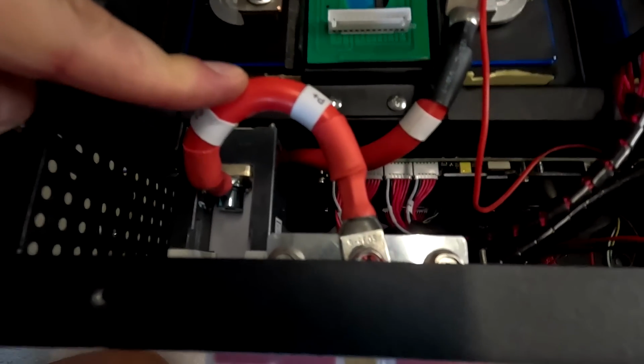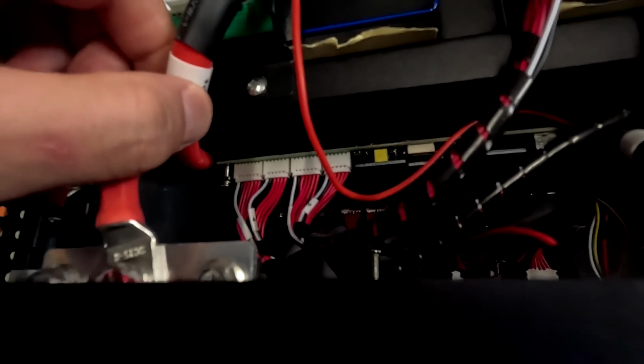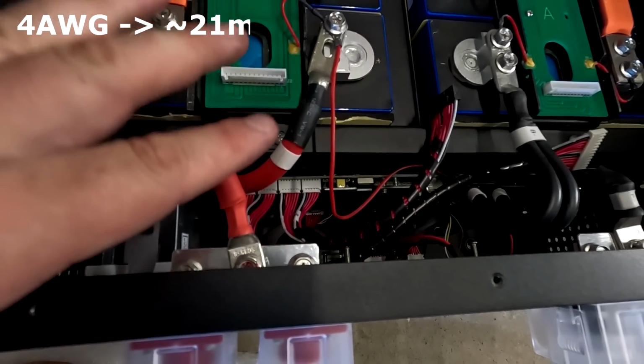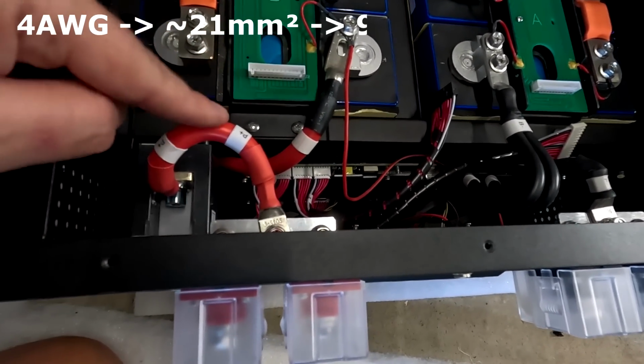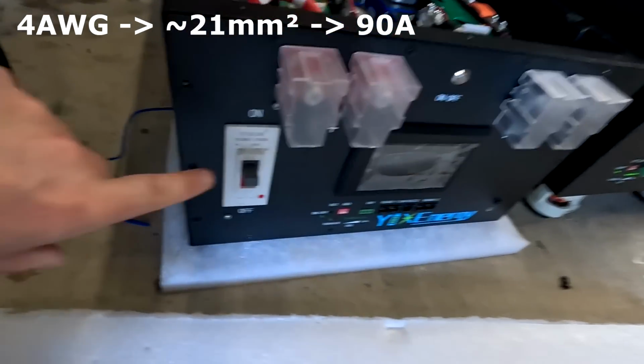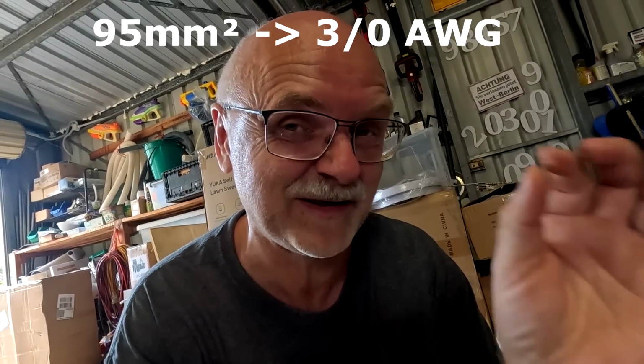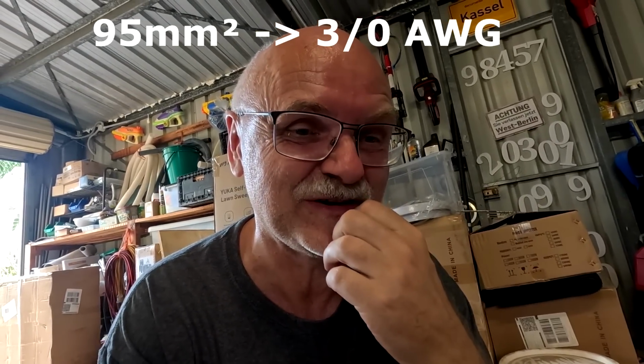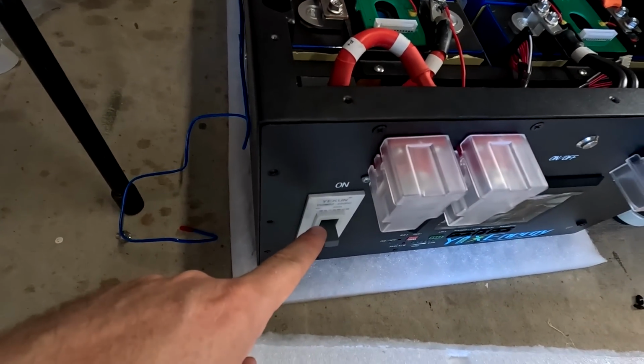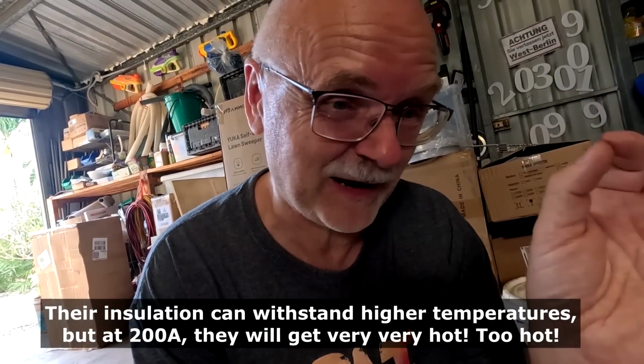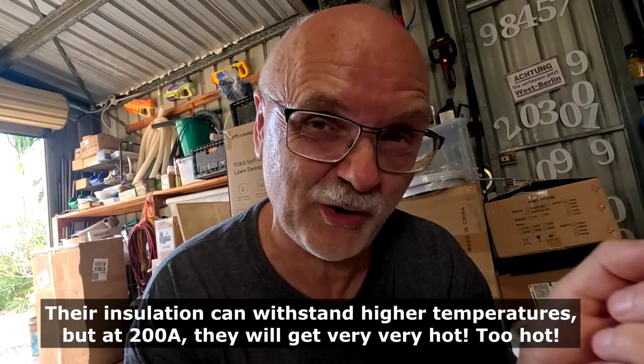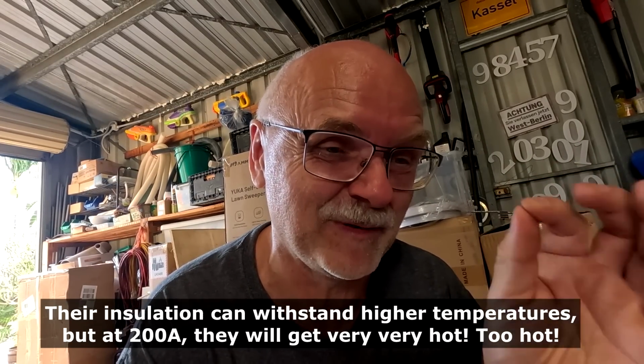And even worse for the positive, because the positive is a, what was it, 4 gauge wire, exactly, 4 gauge wire, which is around only 20 square millimeter of cable. So this one will actually start burning first. And for a 250 amp circuit breaker, they need to have at least 95 square millimeter of cable. So I'm not sure why they use a 20 millimeter cable instead of 95. So these cables need to be longer and need to be upgraded to the correct size to match this circuit breaker. I know these are silicone cables, so they can carry a bit more current, and they're also very short. But still a 25 square millimeter cable and 200 amps or even 250 amps, I don't like.